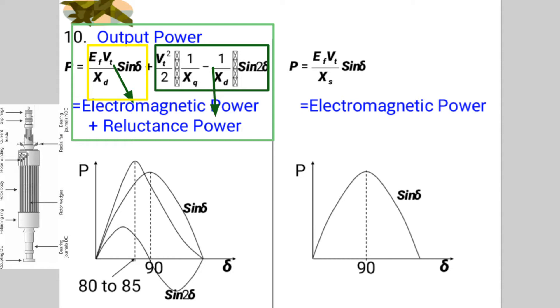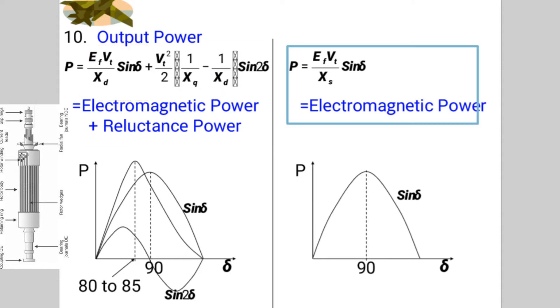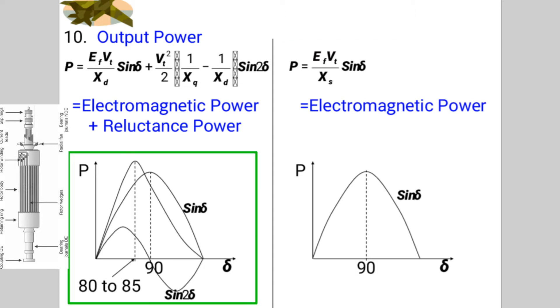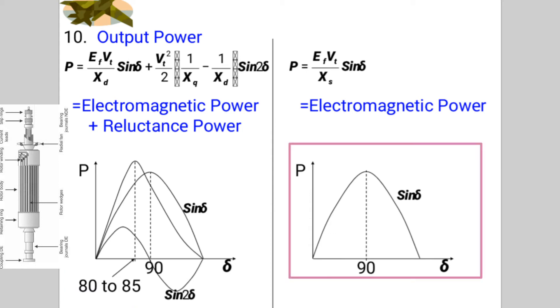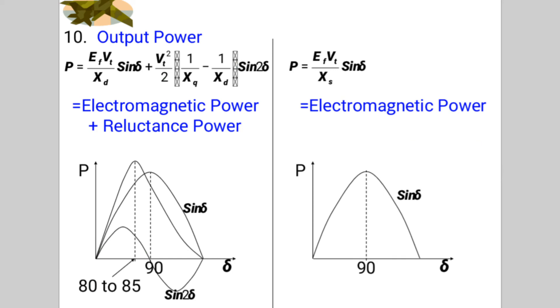Output power is the sum of electromagnetic power and reluctance power, while in cylindrical only EMF power. Here power angle sine delta is from 80 to 85 degrees. Here it is nearer to 88 to 89 degrees.